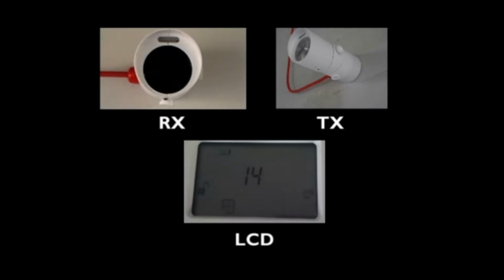Whilst looking at the receiver alignment LEDs, or alignment value, select one thumb wheel and rotate it 1/4 of a turn and let go. Amber flashes on the receiver indicate the signal is reducing and the movement was in the wrong direction. There will be a corresponding decrease of the alignment value on the LCD.